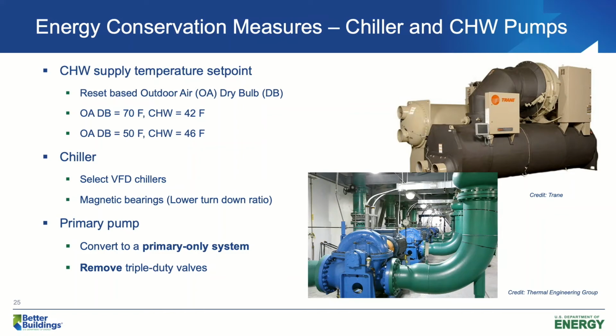Primary pumps. If your system is a primary and secondary setup, we recommend you change that to a primary only configuration. This way, we will have fewer pumps to maintain, and you will have a lot of pump energy savings.